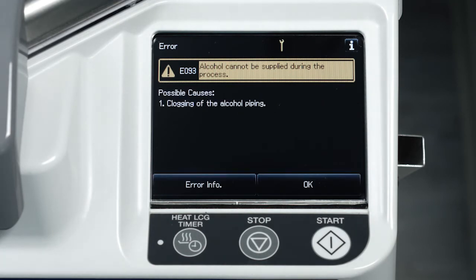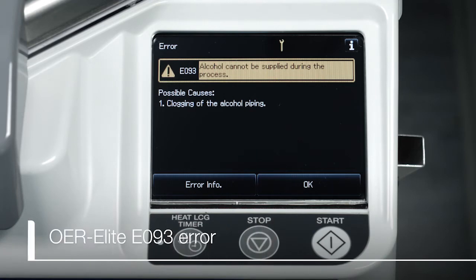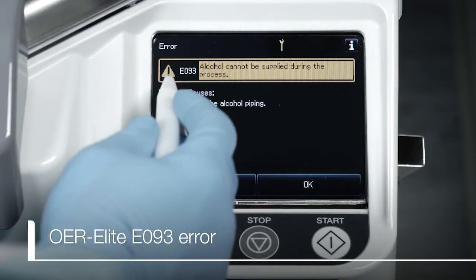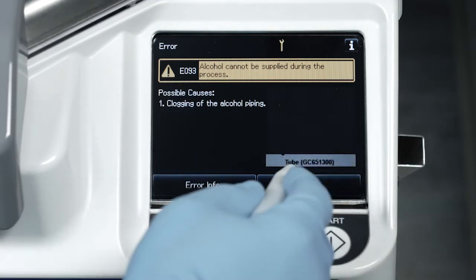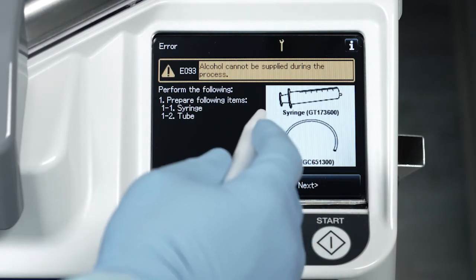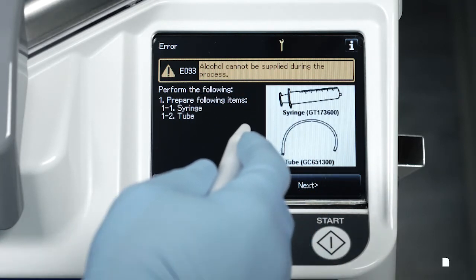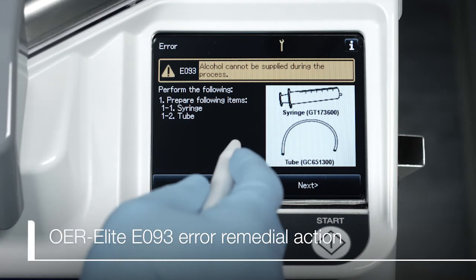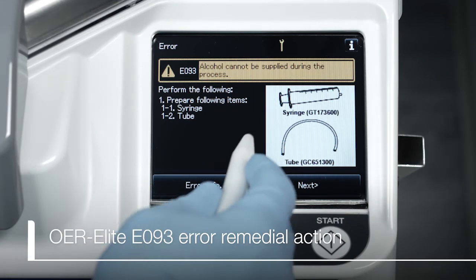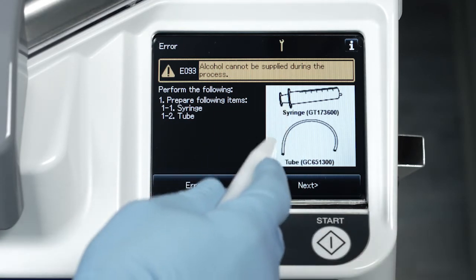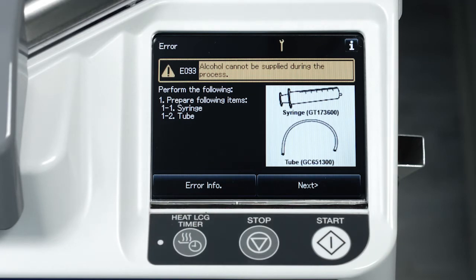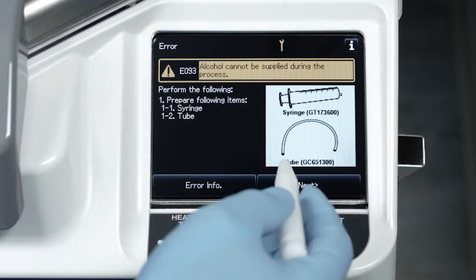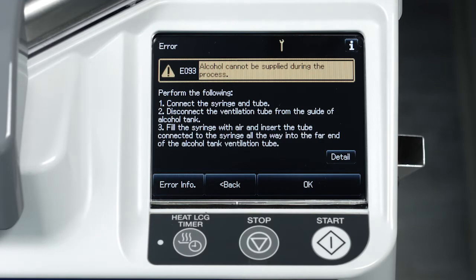Once the stop button is pressed on the OER-Elite display, the E093 error code will appear. Press the OK button. The troubleshooting guide will now display. To resolve this issue, the alcohol line must be primed on the OER-Elite. Obtain the syringe and tube as indicated on the troubleshooting screen. When ready, press the Next button on the touchscreen.